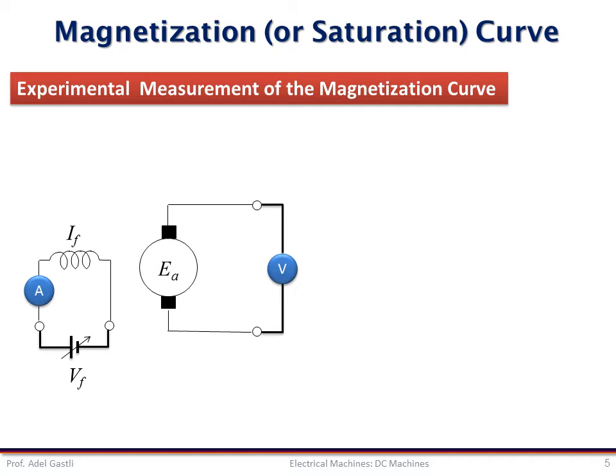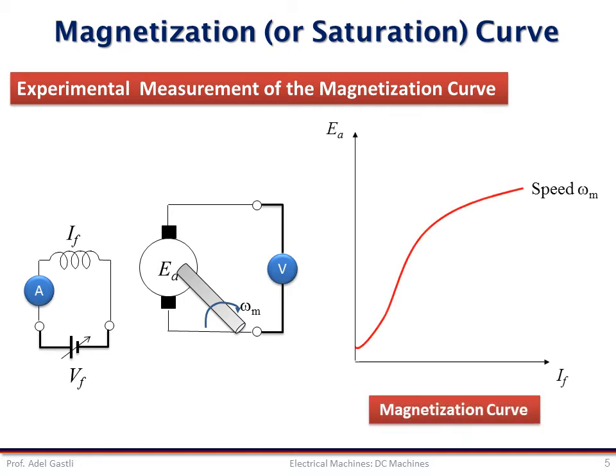Since the armature circuit does not carry any current, the terminal voltage that is measured with the voltmeter is equal to the back EMF. We should drive the machine with a prime mover at the desired speed so that the machine operates as a non-loaded generator. While varying the field current, we take the readings of the ammeter and voltmeter and plot the magnetization curve. This is how we can obtain the magnetization curve of any DC machine at a given speed experimentally.